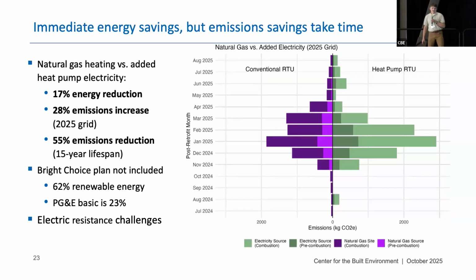Switching from combustion to a heat pump can be up to a 3 times efficiency increase. Digging a little deeper and talking to the owner and engineer, we understood that in the first winter of this system, which is what the case study was based on, they had some issues with electric resistance tripping more often than expected. It's in Oakland, so it shouldn't really be very cold too often - that's something they've been working through.